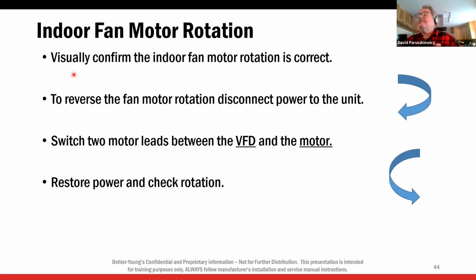All right, so visually confirm the indoor fan motor rotation is correct. Again, it should always be correct. Now, if somebody changes the drive and they don't wire it back in the same way they disconnected it, then the motor could be running backwards. So if you do have a motor running backwards, double check the wiring to and from the drive to make sure it is as it was from the factory. Look at the diagram, make sure yellow's in the right spot, black's in the right spot, blue's in the right spot, both in and out of the drive. Because if you reverse one of those coming out of the drive, that will reverse the motor. All right, make sense?